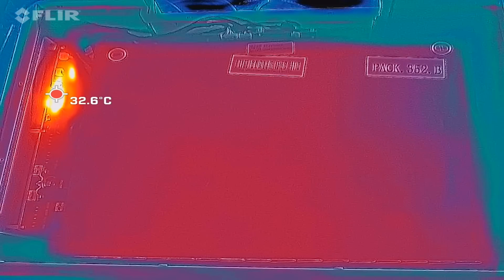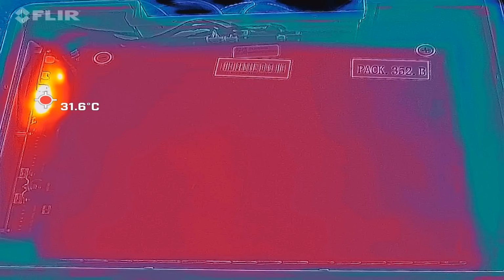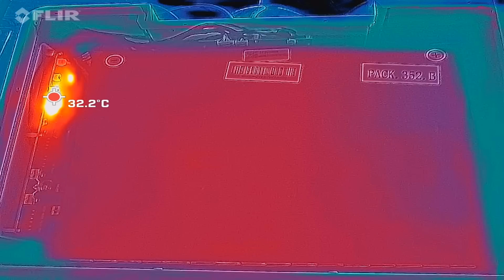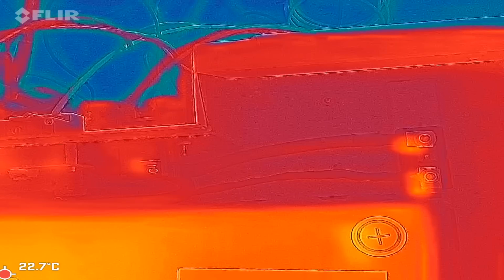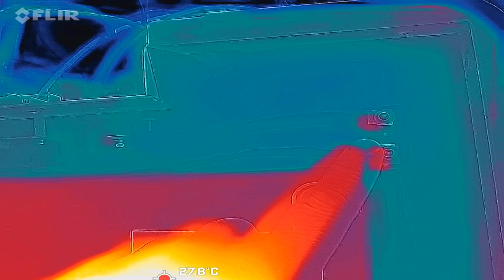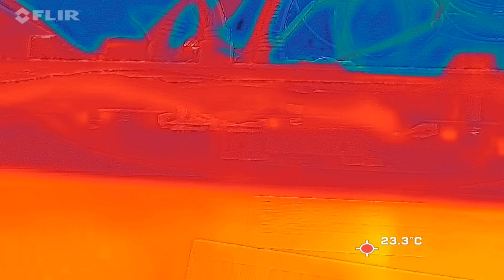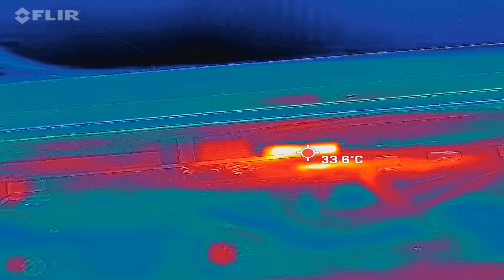So before we start the test, let's have a look with the infrared camera, what we can see. The BMS is obviously a bit warm from charging it up. Battery was on 58%, so I used the power supply to charge it up to 100% now. And this is the back side of the battery pack. You can see the fuse connections there. There's our fuse connection. Breaker and the balance cables, and here is the BMS again, 32 degrees. Okay, nothing to see here. Battery pack is super cool.